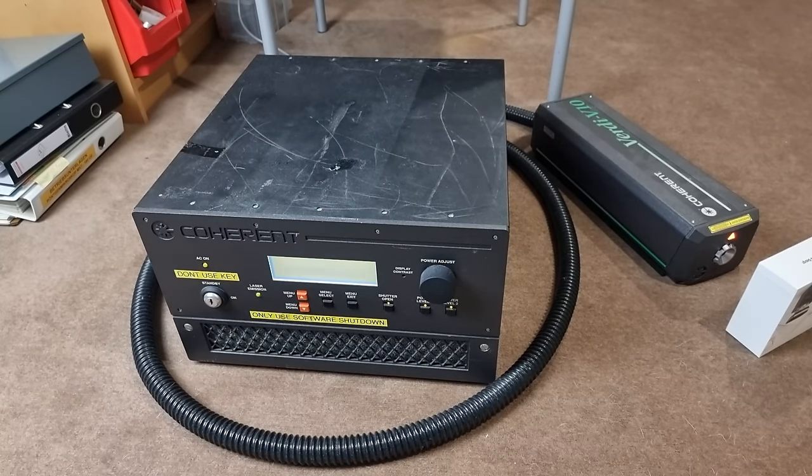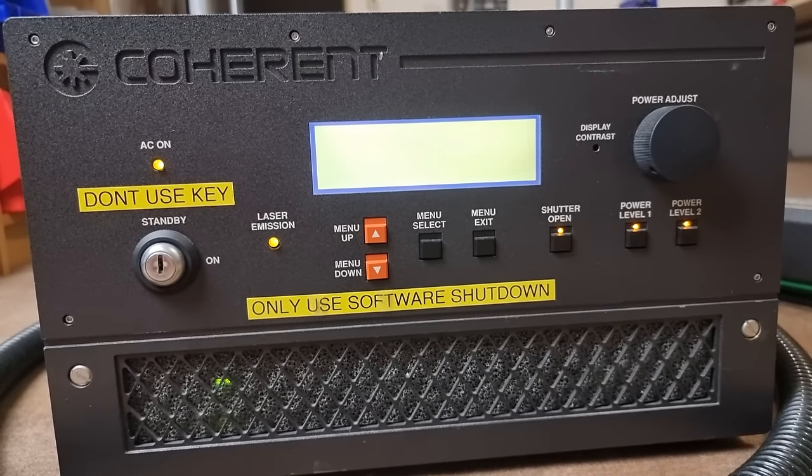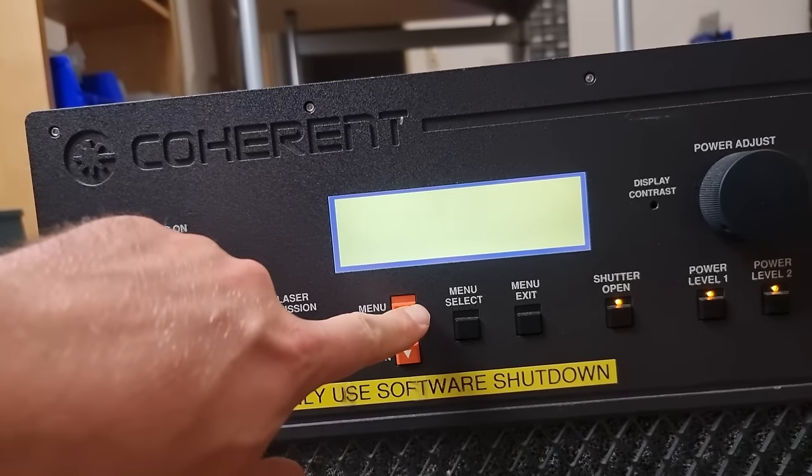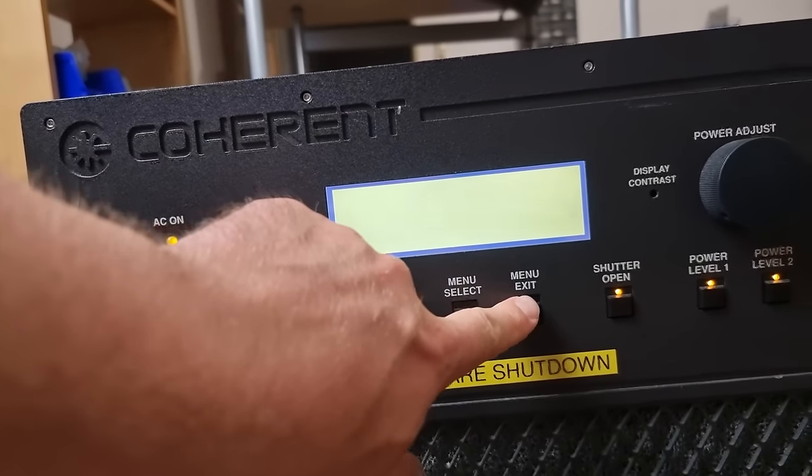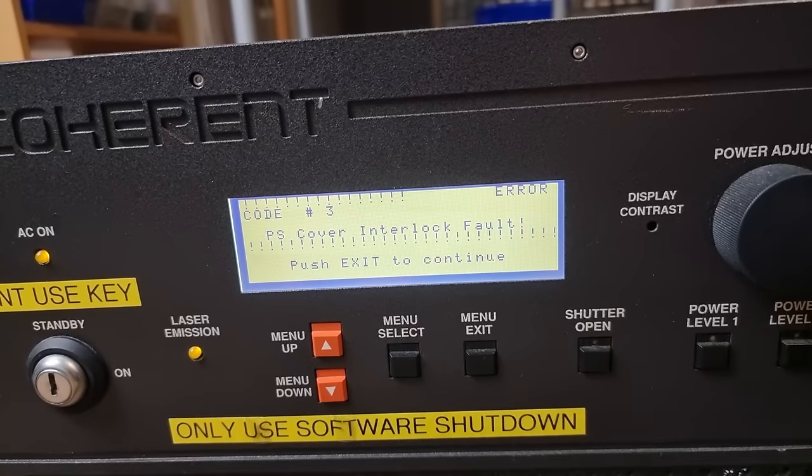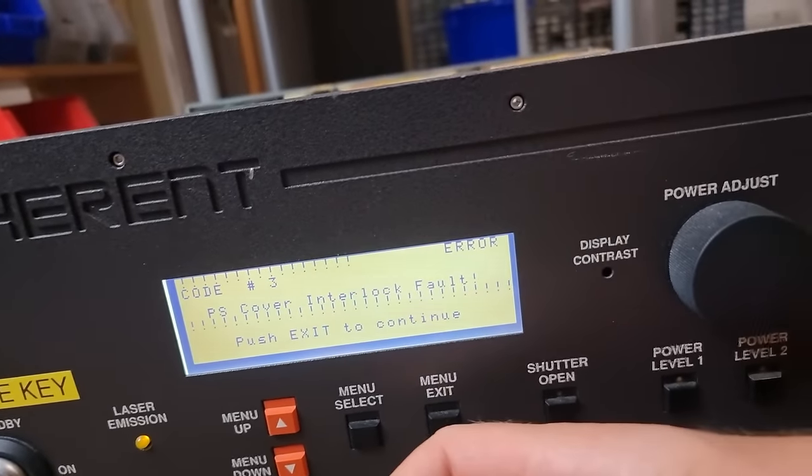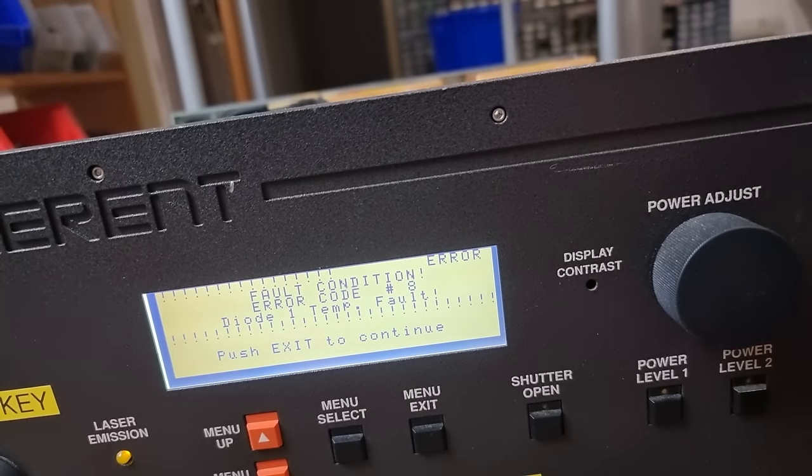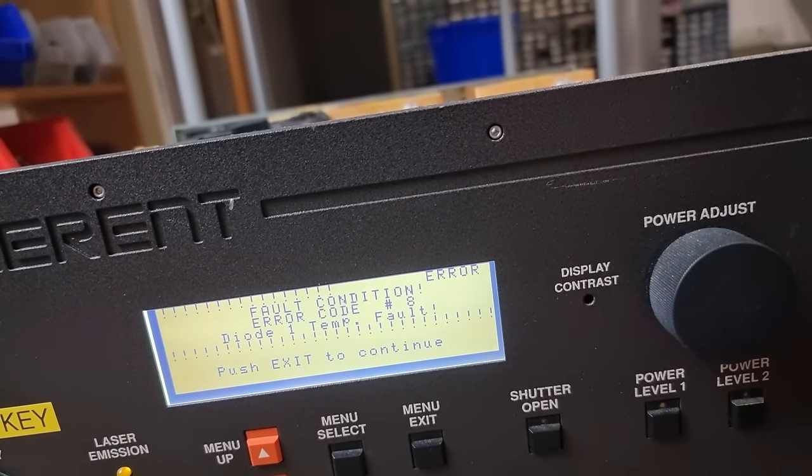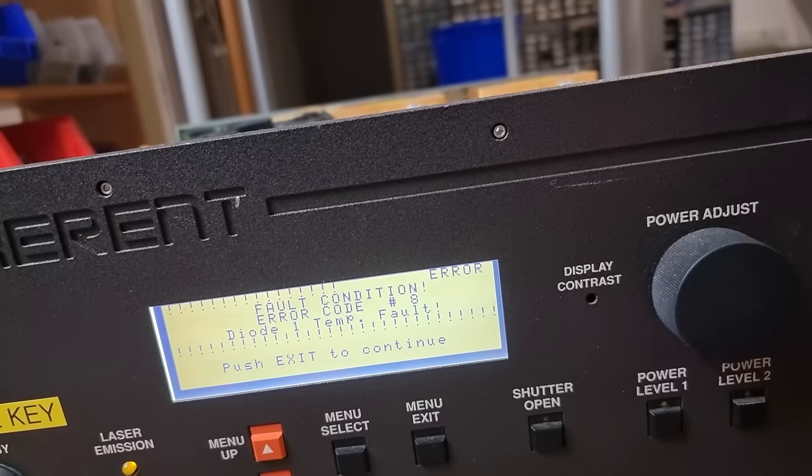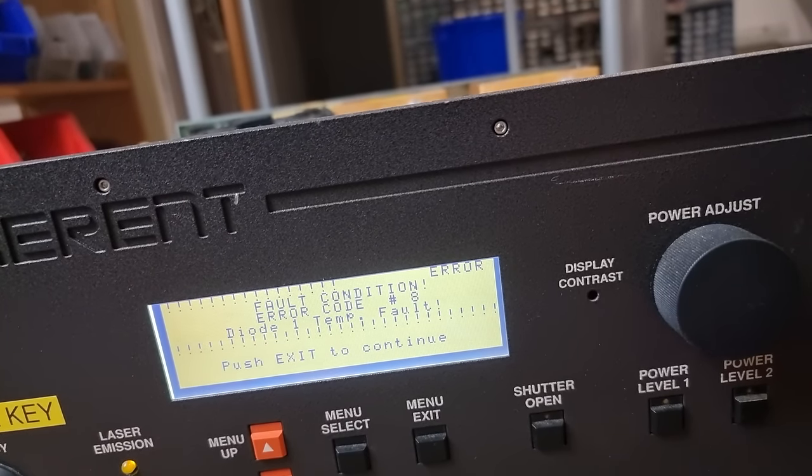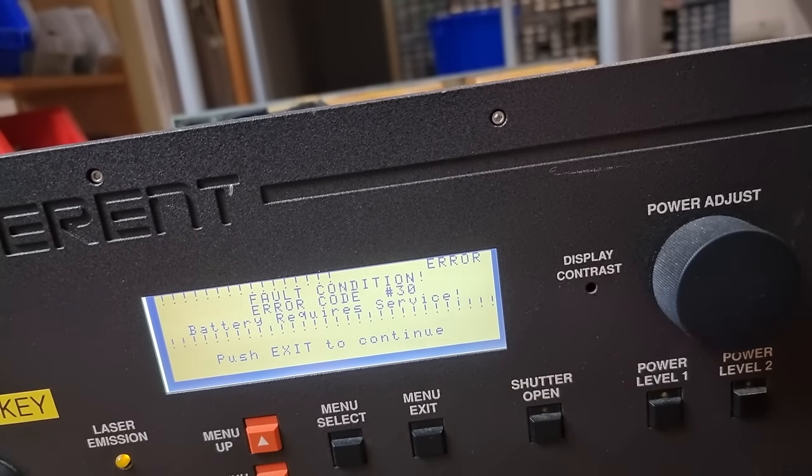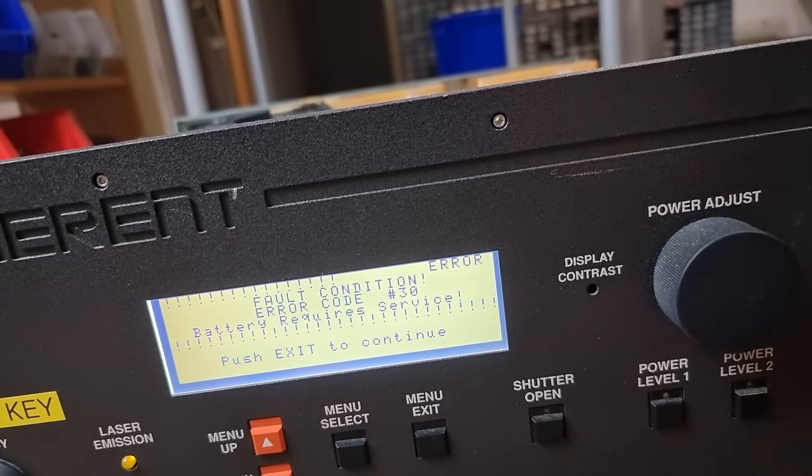It is not happy. If I remember correctly, it was already destined to be scrapped before the neuroscience department adopted and revived it. Now it doesn't display anything anymore most of the time. And if it does, it's throwing its entire repertoire of error codes at me. Whoa, take it easy with the exclamation marks buddy. This is good though, electrical problems are the ones I can fix. It could also have damage to obscure optical components in the head. That would be more challenging.